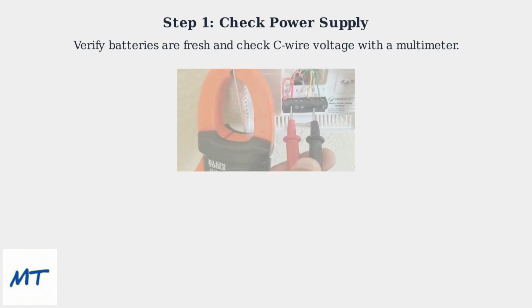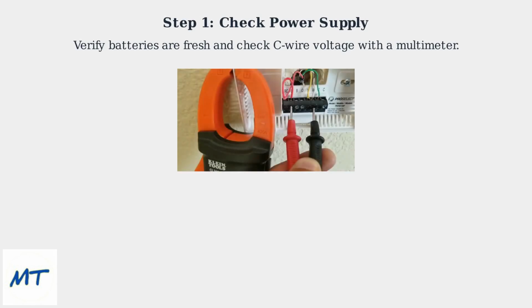Start by checking the power supply. Ensure batteries are fresh and verify C-wire voltage using a multimeter. Then carefully inspect the wiring connections. Ensure wires are properly matched to terminals like R for red hot, W for white heat, Y for yellow cool, G for green fan, and C for common. Next, review and correct the thermostat settings. Verify the system type is set correctly and ensure temperature limits are appropriate. Finally, perform a reset if the issue persists. Remove batteries for 30 seconds or follow the specific reset procedure for your model.